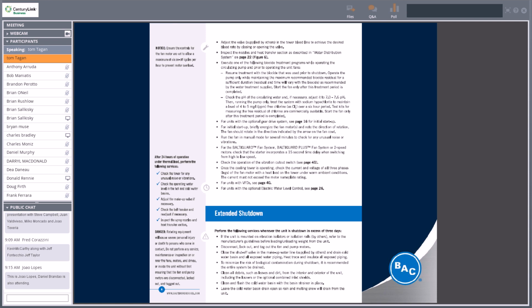The next page here mentioned the extended shutdown. So it's going to recommend that as you shut down for the season, you're going to disconnect and lock out the fan motor, obviously. You close the shutoff valve in the makeup water line. You want to drain the tower, and that's to minimize any biological growth.